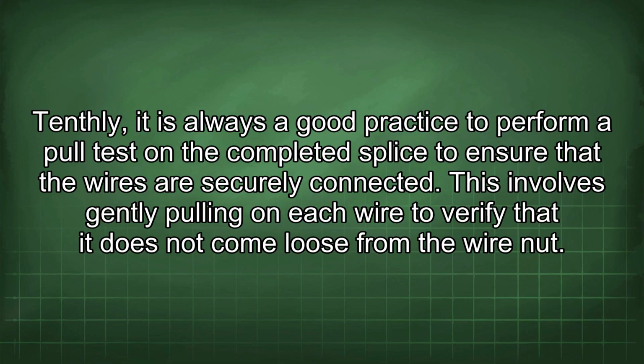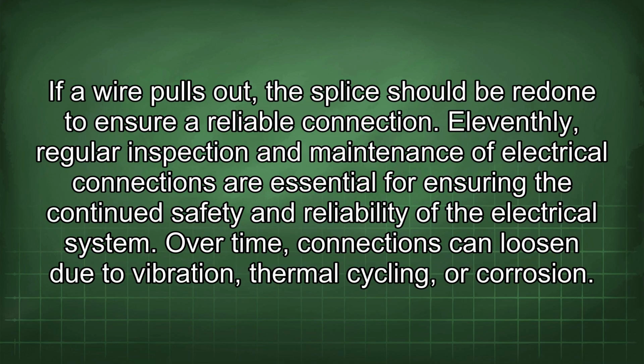Tenthly, it is always a good practice to perform a pull test on the completed splice to ensure that the wires are securely connected. This involves gently pulling on each wire to verify that it does not come loose from the wire nut. If a wire pulls out, the splice should be redone to ensure a reliable connection.